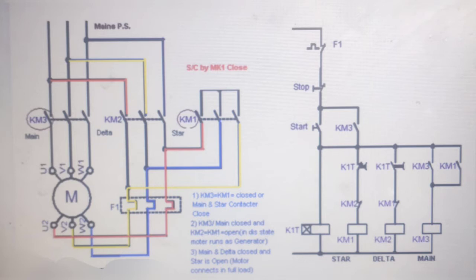The size of the contactor is smaller compared to the direct online starter because the load current is reduced in contactors. There are two contactors that are closed during run, often referred to as the main contactor and the delta contactor. These are AC3 rated at 58 percent of the current rating of the motor, that means one third.